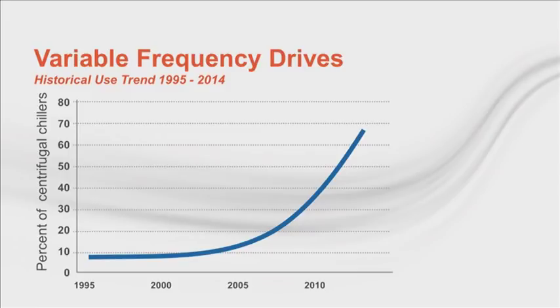Now, what do we expect to see in the future? There are two possible scenarios here. Let's look at the first. One possible scenario is continued growth towards 100%. Now, hitting the 100% mark seems unlikely when you consider VFDs are not advantageous in all applications. For example, climates that offer little ambient relief, areas with high demand rates, multiple chiller plants, high or even sometimes medium voltage applications, and others that do not provide situations that would leverage VFD benefits.